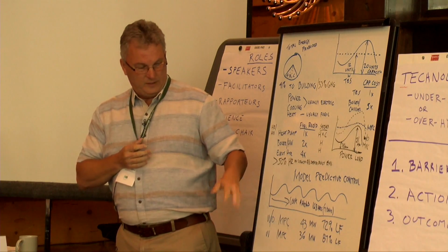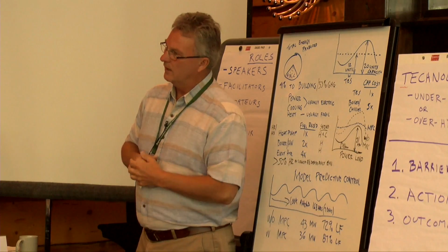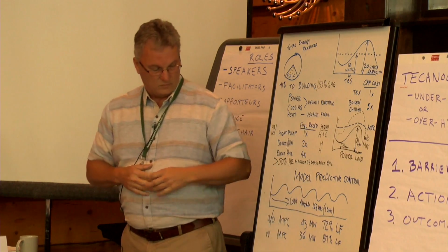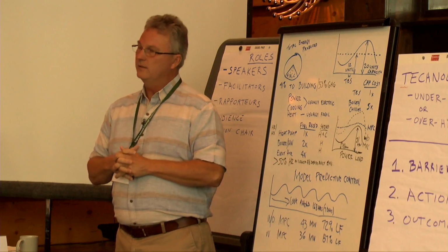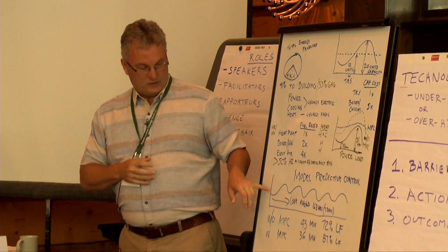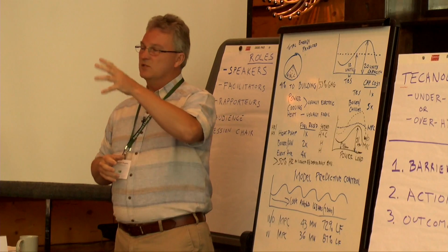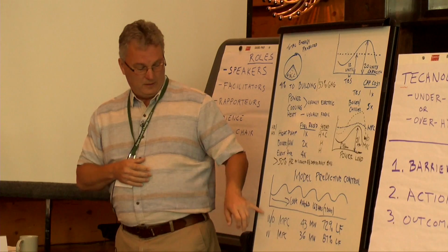So we invented a program based on model predictive control where we're looking hour by hour constantly 7 days in advance, so as to always grab a weekend since the load patterns change, predict what the loads are. We predict what energy prices will be. We have a deregulated electricity market in California where day-ahead prices vary by hour. And so based on the distribution of electricity prices and our projected loads, the computer finds the optimal way to dispatch the plant, when to do heat pumping, heating, cooling, when to take and put from thermal storage.